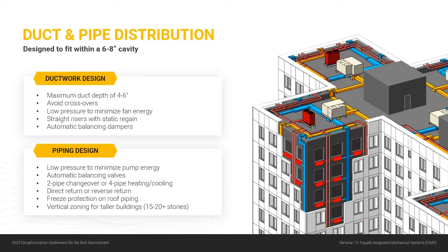So the piping that's inside of the facade will not be exposed to freezing conditions, but piping on the roof could be. So conventional methods of freeze protection, glycol, antifreeze, or heat tracing, anything like that, would need to be considered. And then again, as with any conventional hydronic system, once you get to taller buildings, you do need to consider zoning it vertically. And that typically happens when you get to buildings in the 15 to 20-story range.